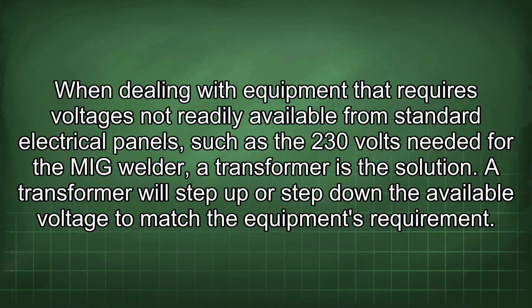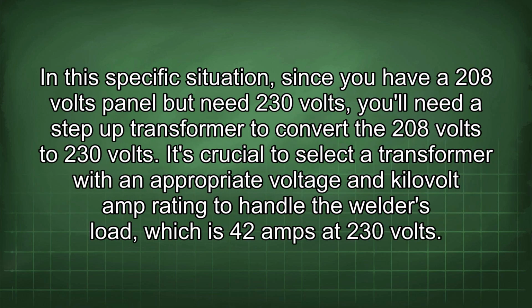When dealing with equipment that requires voltages not readily available from standard electrical panels, such as the 230 volts needed for the MIG welder, a transformer is the solution. A transformer will step up or step down the available voltage to match the equipment's requirement. In this specific situation, since you have a 208 volts panel but need 230 volts, you'll need a step-up transformer to convert the 208 volts to 230 volts. It's crucial to select a transformer with an appropriate voltage and kilovolt amp rating to handle the welder's load, which is 42 amps at 230 volts.